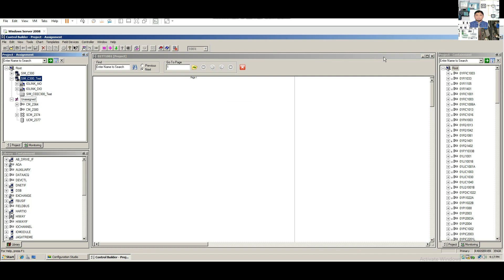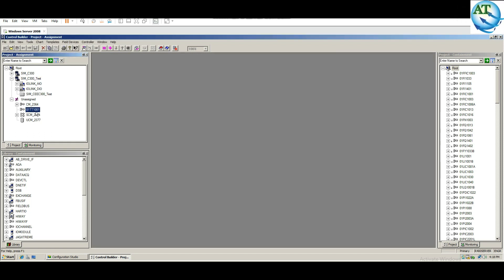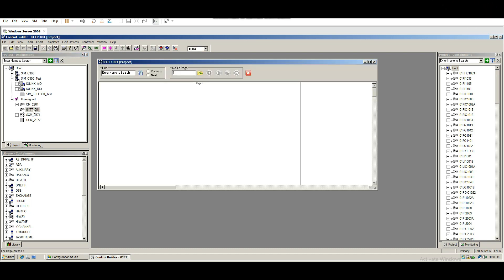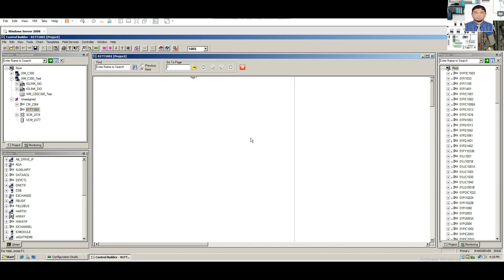The tag is now in the unassigned state, so close or save it. You can see the new control module program that we have inserted. Double-click on the program. Now we have to select the input/output card that we want to connect to the field instrument. See the IO Link — it is the analog input. In IO Link 1, different types of analog cards are available: non-redundant and redundant. If you think this is an important tag, you can put it in the redundant module. So we select the redundant module and double-click.